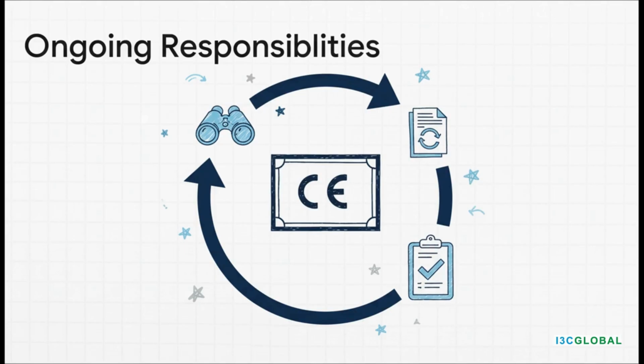You're now on the hook for continuous post-market surveillance, which means you have to keep a close eye on how your device performs out in the real world. You've got to keep your technical file updated, submit periodic safety update reports, and have a rock-solid system for reporting any incidents. You have to think of compliance as a living, breathing process, not a box you check just once.